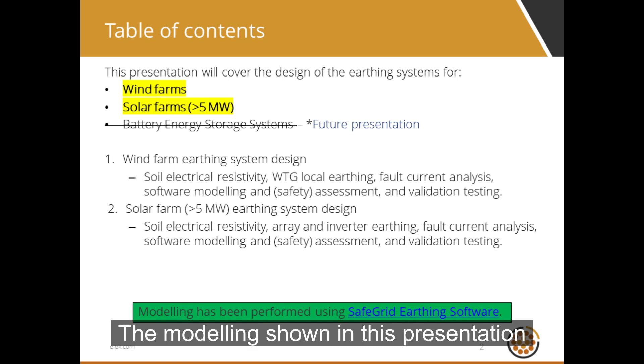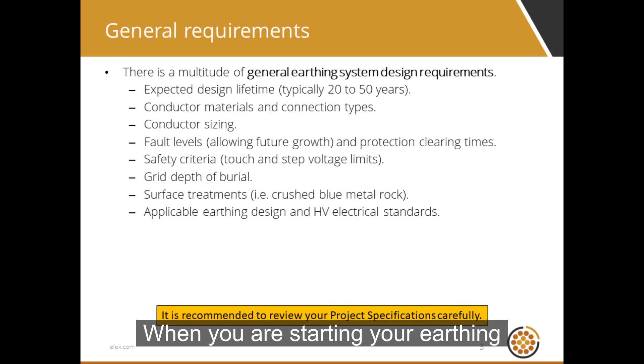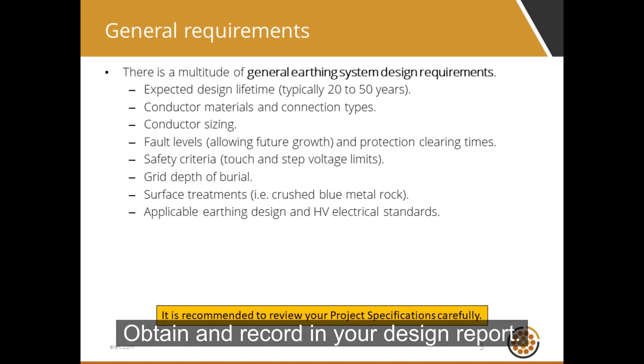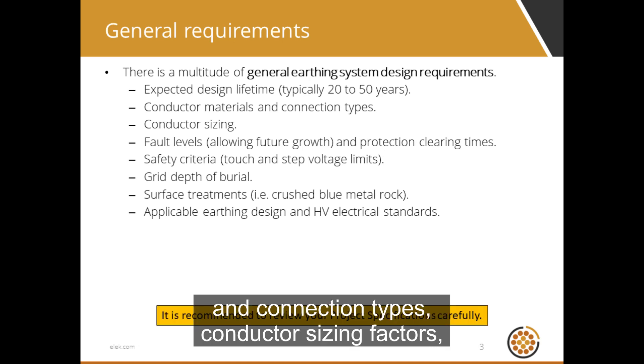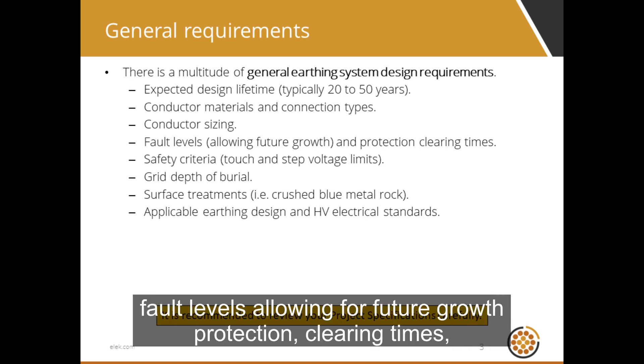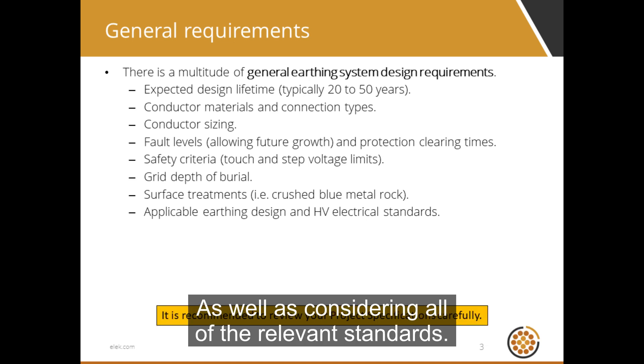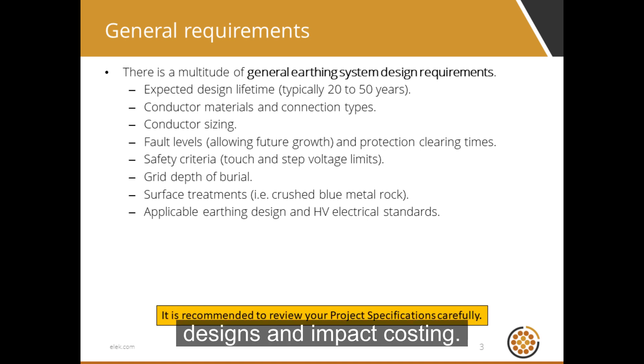The modeling shown in this presentation was performed using SAFE Grid earthing software. When starting your earthing designs, make sure you check the project specifications very carefully. Obtain and record in your design report important factors including expected design life, conductor materials and connection types, conductor sizing factors, fault levels allowing for future growth, protection clearing times, safety criteria, grid depth of burial, and requirements for surface treatments, as well as all relevant standards. These factors will significantly affect your earthing designs and impact costing.